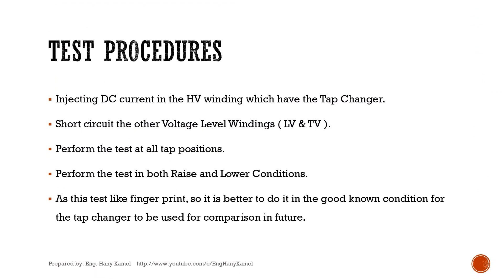To perform dynamic resistance measurement, inject DC current in the high voltage winding which has the tap changer, and short-circuit the other voltage level windings — low voltage and tertiary if available. Perform the test at all tap positions and in both raise and lower conditions. As this test is like a fingerprint, it is better to do it in a known good condition for the tap changer, to be used for comparison in the future.